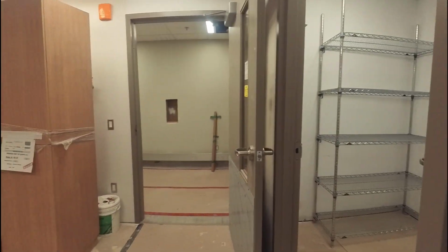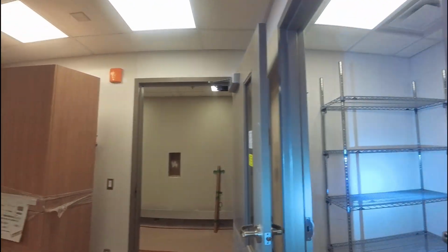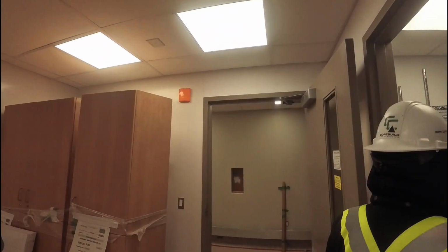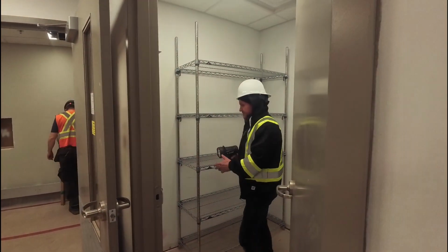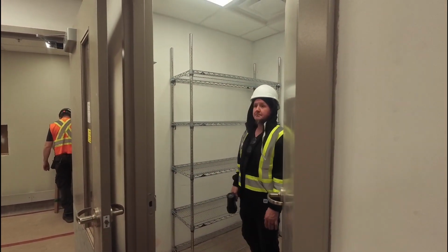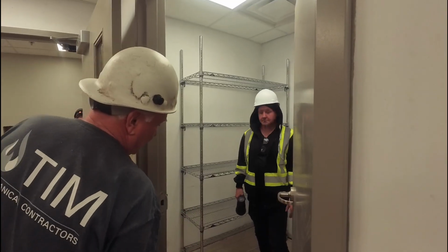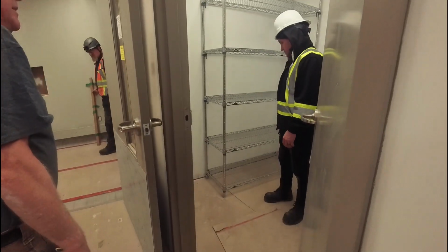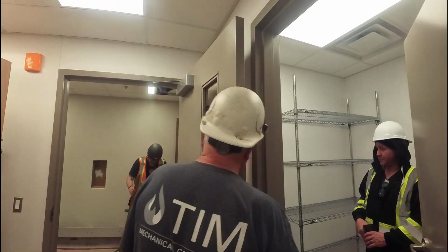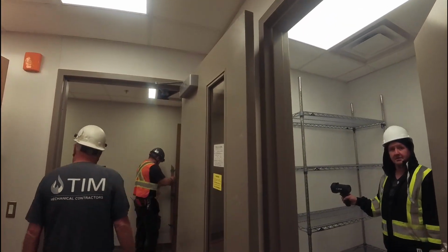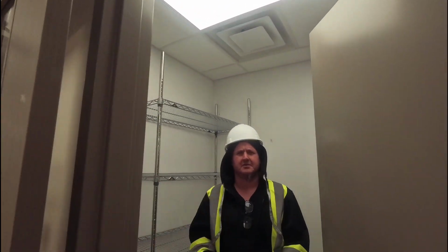That shelf can't be there. That shelf's gotta be moved. Yeah, it's too close to the electrical panel. There has to be meter clearance. They must be doing something more to the bottom of that room anyway, and before they go for it, there has to be a piece of baseboard. So it's gotta sit way back here, right? That'd be meter clearance in front, 3 feet.